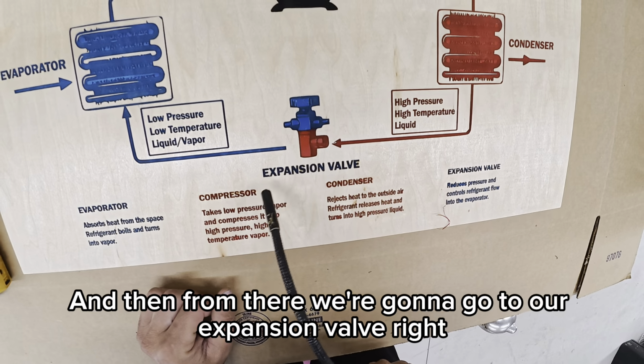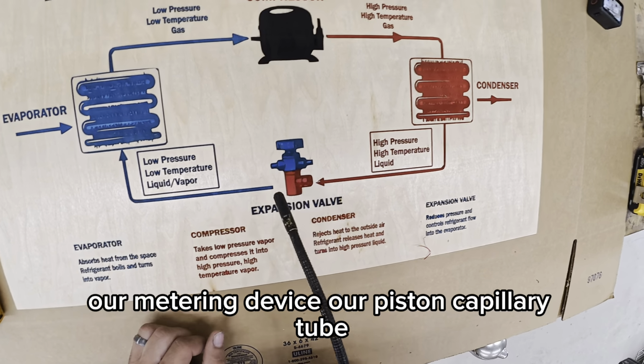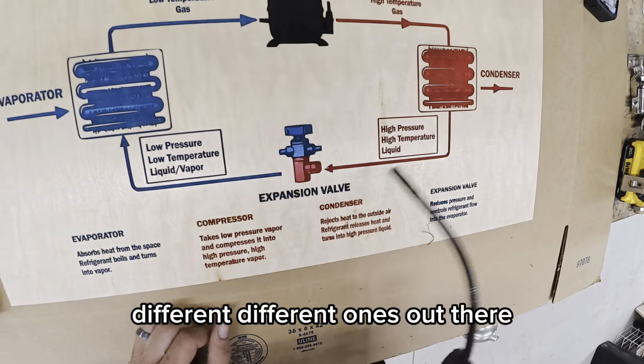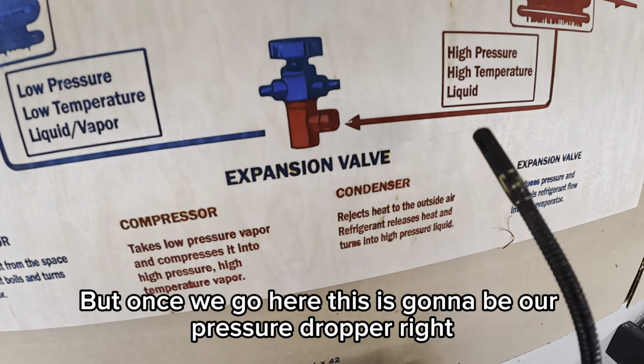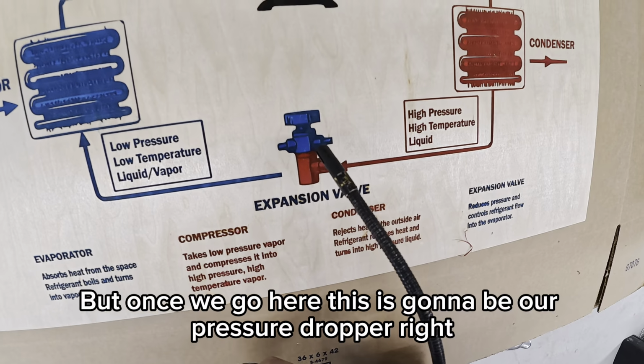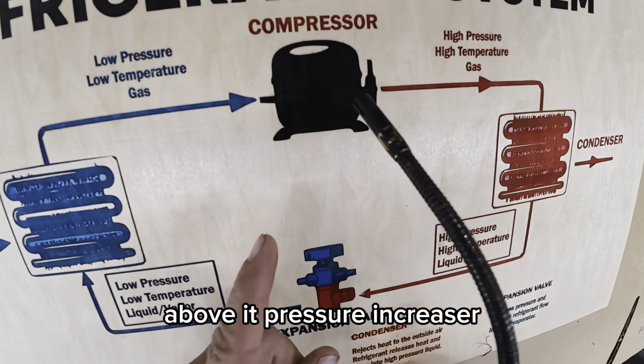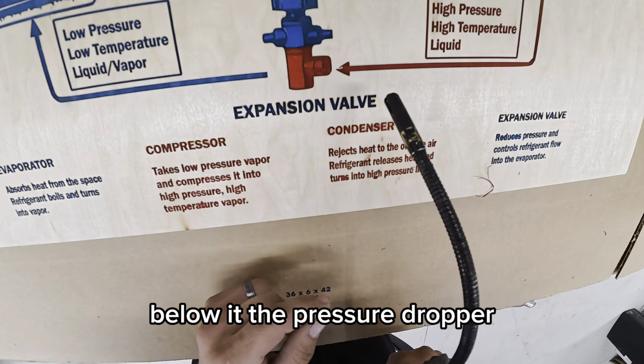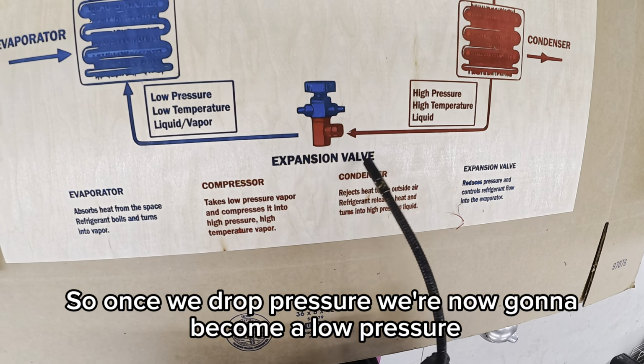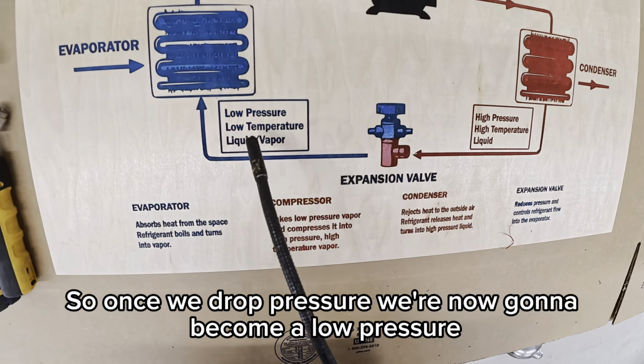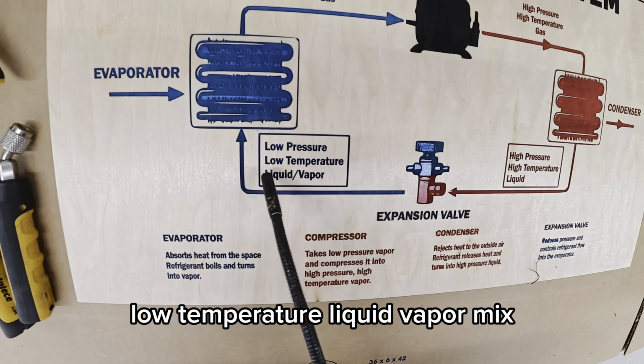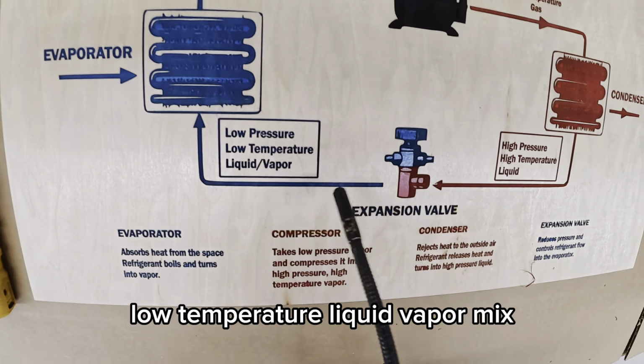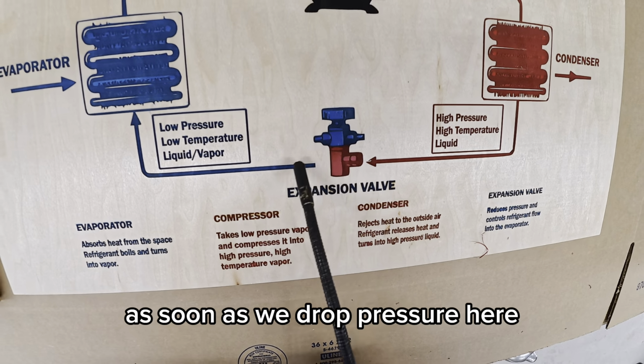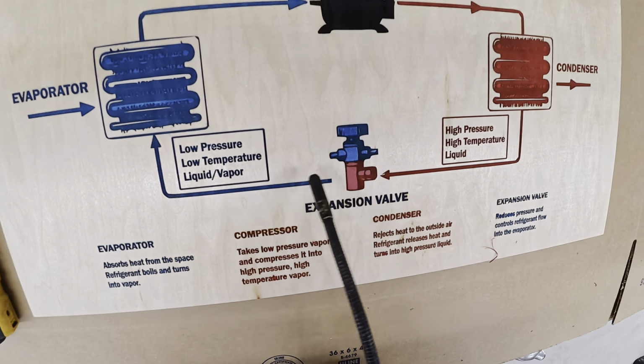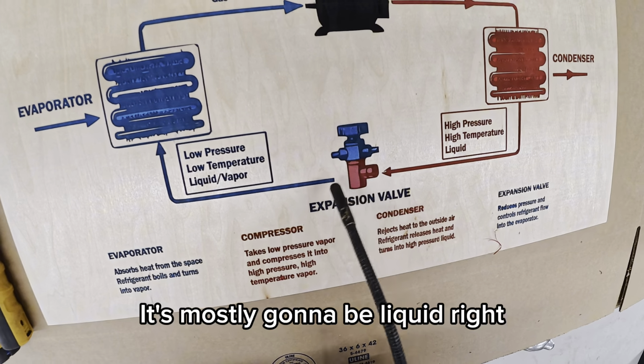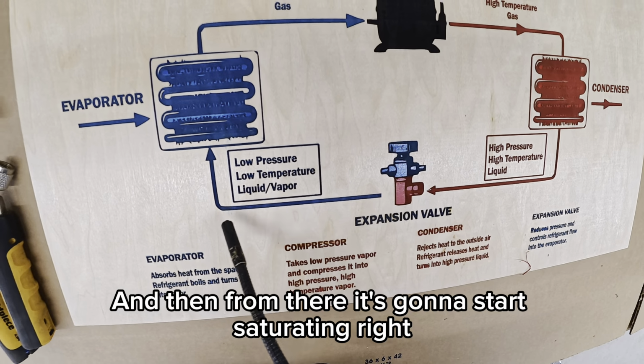And then from there, we're going to go to our expansion valve, right? Our metering device, our piston, capillary tube, different ones out there. But once we go here, this is going to be our pressure dropper, right? Above it, pressure increaser. Below it, the pressure dropper. So once we drop pressure, we're now going to become a low pressure, low temperature, liquid vapor mix. As soon as we drop pressure here, we're going to start boiling off. It's mostly going to be liquid, right? And then from there, it's going to start saturating, right?